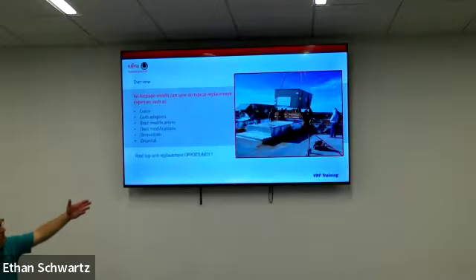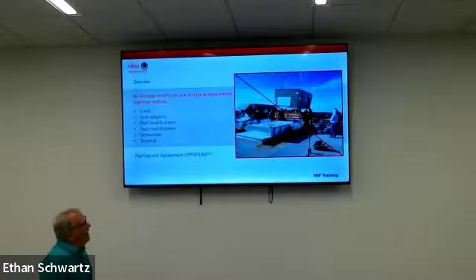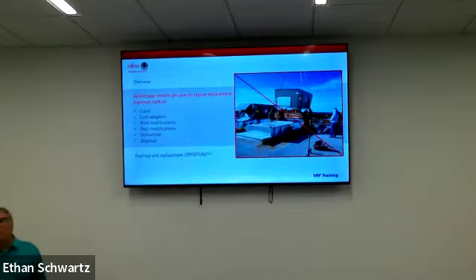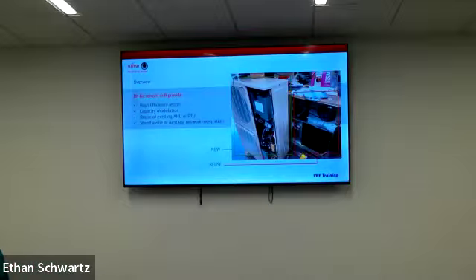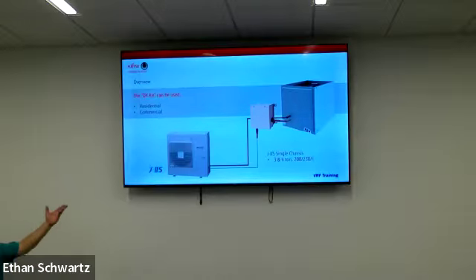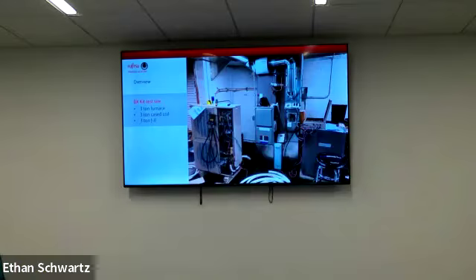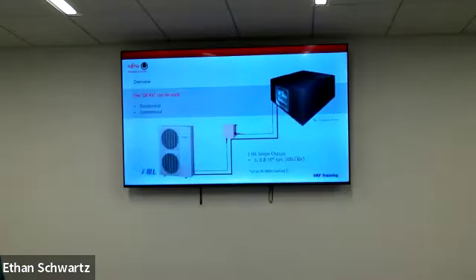But if you have a rooftop unit and the rooftop unit is delayed and they've got to be back in operation soon, then we most likely will have the outdoor unit in stock at one of our warehouses with Fujitsu and a DX kit, and you could begin piping and getting them back in operation. So that's kind of what that looks like. I've done a J2S, that's the very original, on a 3-ton, with just an Aspen replacement coil. So it's not just for big stuff.